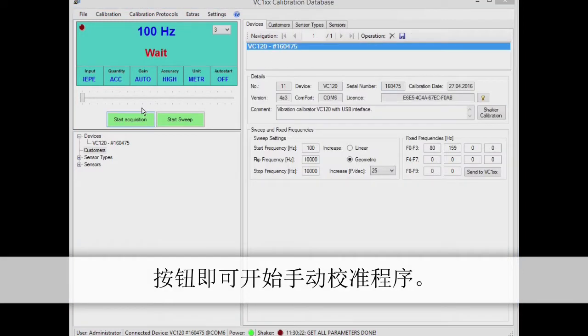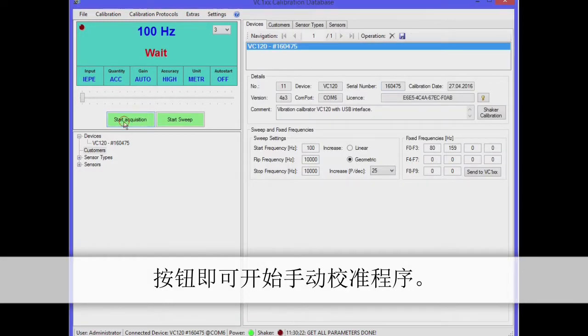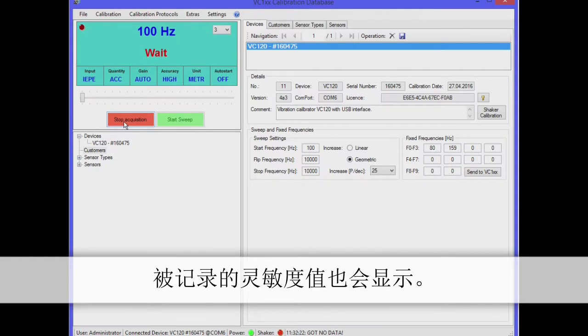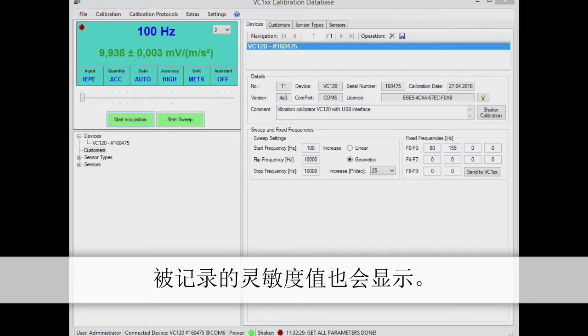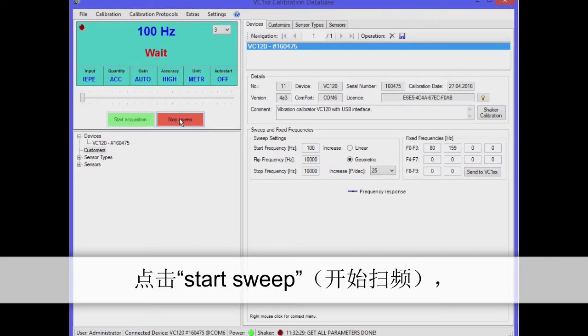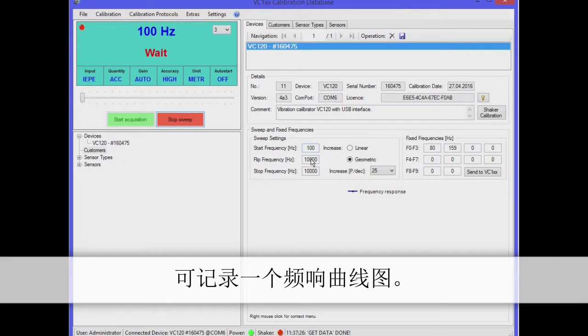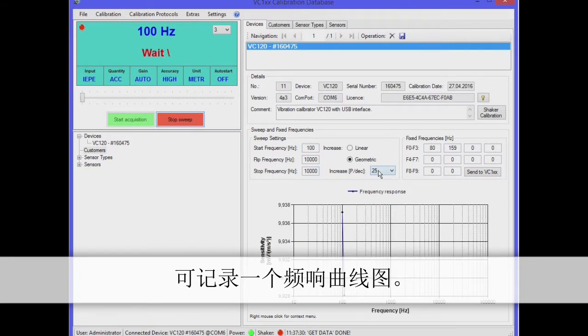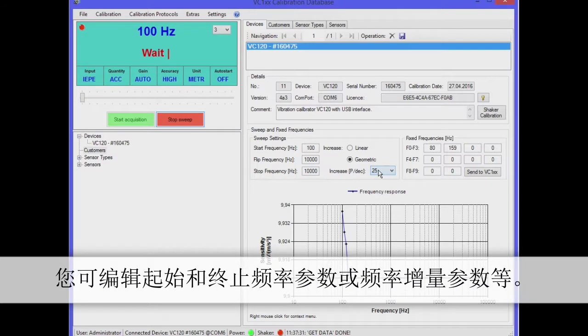Click on Start Acquisition to start a manual calibration. The recorded sensitivity will appear on the screen. By pressing Start Sweep you can record a frequency response graph. You can edit parameters such as Start and Stop Frequency or Frequency Increment. Click on the diagram to select axis scaling or export options.